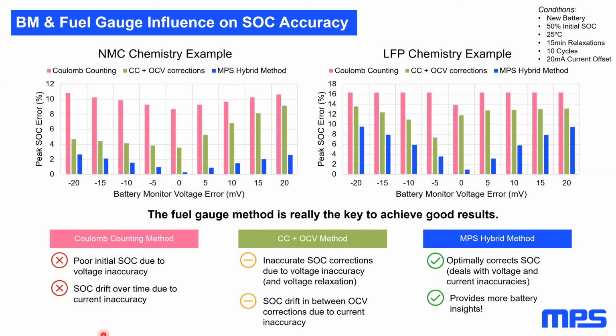The Coulomb counting method, shown in pink, relies on voltage only for the initial state of charge estimate. Therefore, any error in the initial SOC will not be corrected since it runs open loop. Additionally, any error in the current measurement will cause the SOC to accumulate and drift over time. For these reasons, the Coulomb counting method does not provide good results.